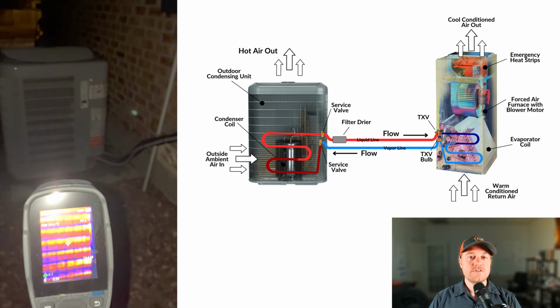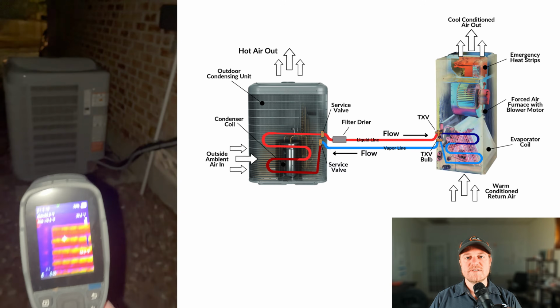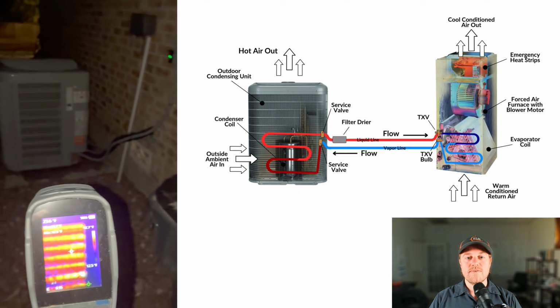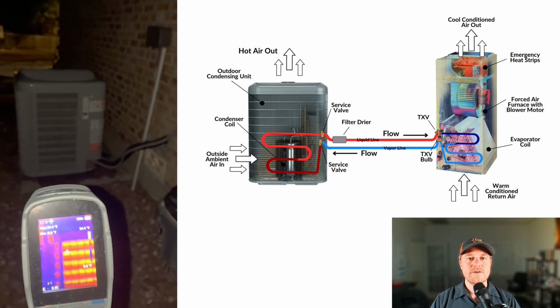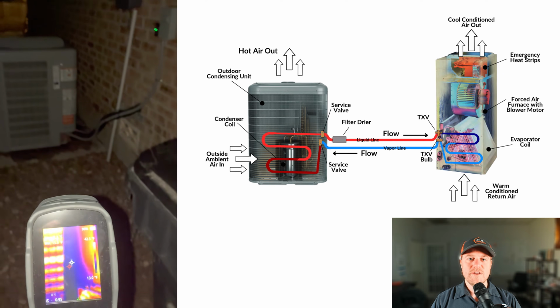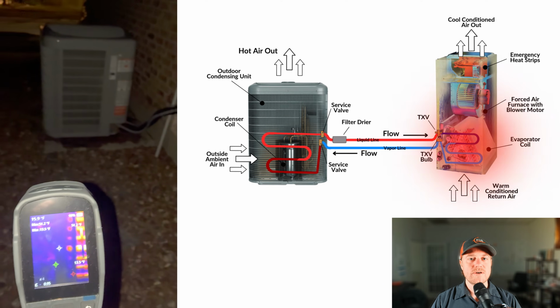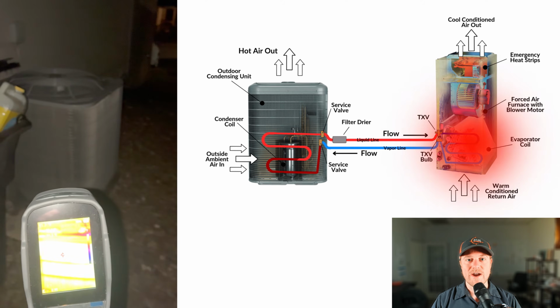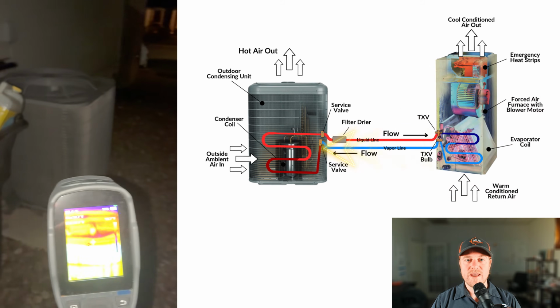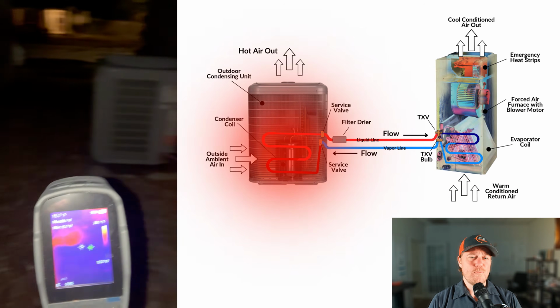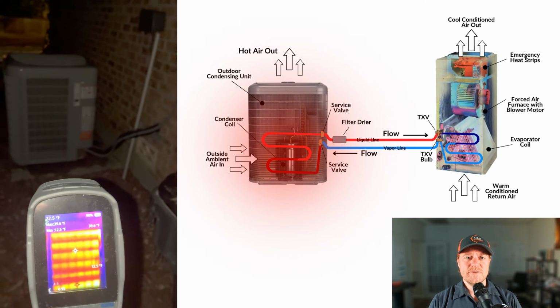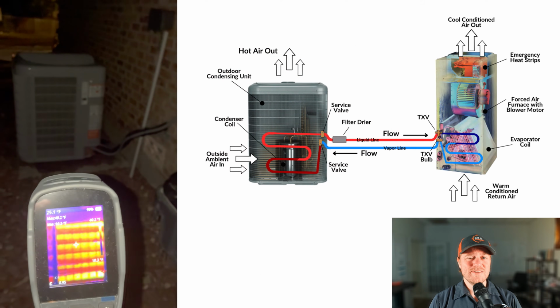And that's exactly what you saw my system just do. In some systems, you can hear a loud clunk noise when it reverses. It's surprising to see how quickly the coils are warming up. What's happening here is the indoor evaporator coil is now absorbing the heat from inside your house. Then it's sending it back to the outdoor unit. Then the heat pump can now melt all that ice. Once all the ice is melted, the reversing valve will turn it back into heating mode.